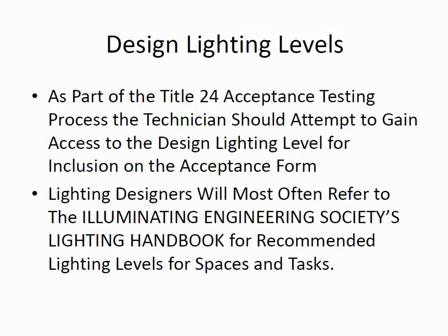Under no circumstances are you actually required to supply design illuminance levels on any of the compliance forms under the 2013 code. I don't believe there's any spot for it under the 2016 either. An acceptance test technician is actually better off if you don't supply design lighting level value. There is a slot for it on a portion of the automatic daylighting form, but it doesn't have to be filled out.